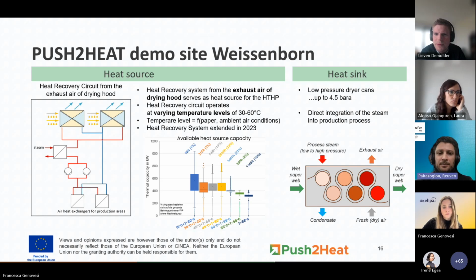Nevertheless, the full load operation hours are assessed at 4,000 hours per year, during which this waste heat is available at different temperature levels and capacities. So in a nutshell, assessing the waste heat potential is very crucial for designing any kind of system, also taking into account that recovery circuits can possibly be extended. This was taken into account, and it's crucial for designing any kind of heat upgrade system.